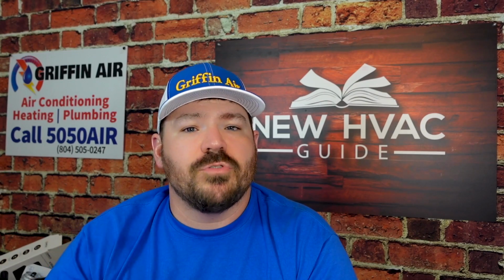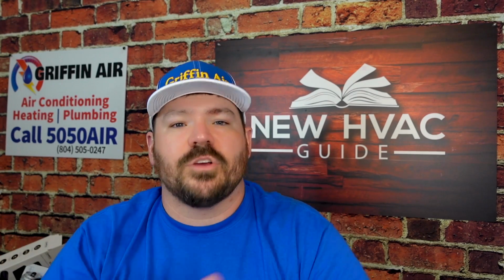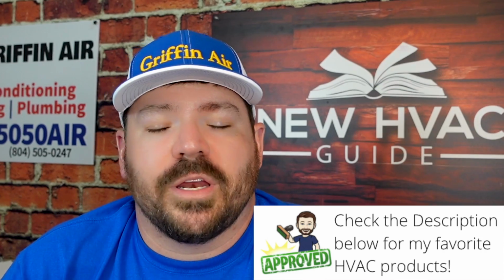I thought it was very unique how Bosch was able to come out with this technology, and they've got this inverter compressor. It can ramp up and down, but instead of the indoor and outdoor units talking with the thermostat and communicating, it used other technologies to ramp up and down. And so I know Bosch basically monitors the pressure coming back from the evaporator coil and the temperature that you are setting it at, its target temperature. It will ramp up and down based on that. I don't know how these are going to work in contrast to that.